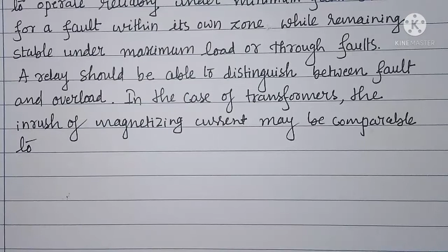A relay should be able to distinguish between fault and overload. In the case of transformers, the inrush of magnetizing current may be comparable to the fault current, being 6 to 7 times the full load current. The relay should not operate for inrush currents.